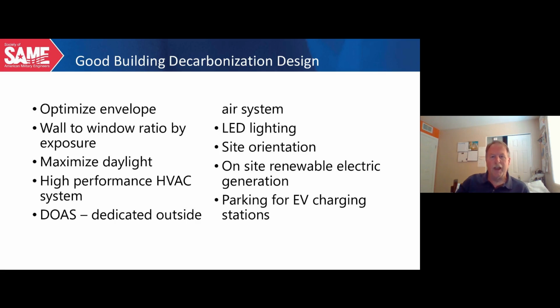We want to focus ourselves on high performance air conditioning systems. And I would bring two of those to your attention: radiant heating and cooling panels at the ceiling, and also chilled beam systems. They both have the ability to have zero terminal airside horsepower at the zone level. So they're different than any other systems that we've had available in the past. Hopefully you've had experience with both of those. Dedicated outside air systems have come to the forefront probably in the past 12 years. One of the advantages of dedicated outside air systems is we get to pre-filter all the outside air that's required for proper ventilation of the building, but we also get to preheat it, pre-cool it, and dehumidify it before we actually send it into the zone.